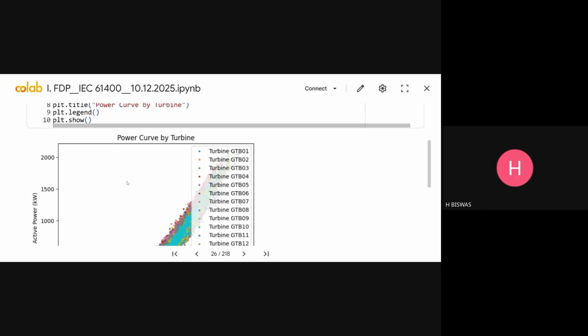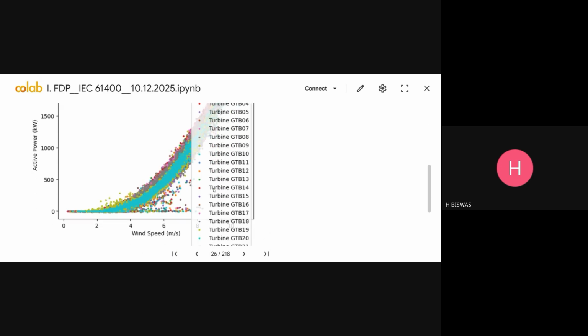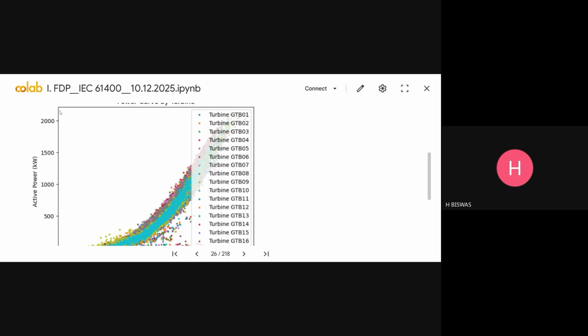Now this is called the power curve by turbine. If you see, this is turbine-wise - every turbine, all 30 turbines, is given. So the power curve is based on wind speed on the horizontal axis, and active power on the vertical axis. This gives you a different flavor. Now, when your turbine is functioning well - this is a 2 megawatt turbine, and we have about 30 of them, so total capacity is slightly over 60 megawatts. Every power curve looks something like that.